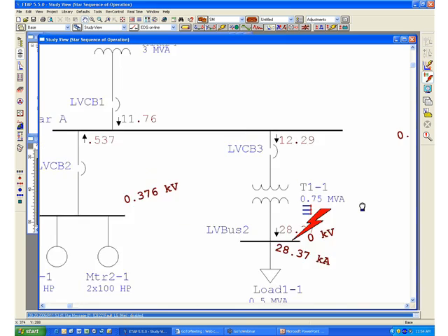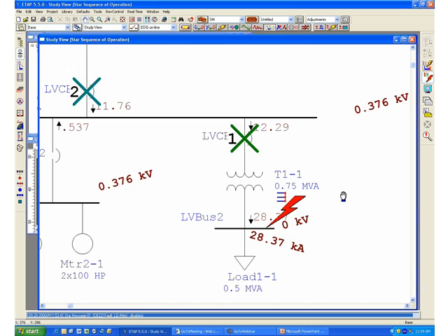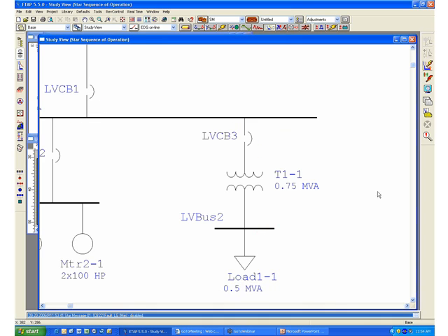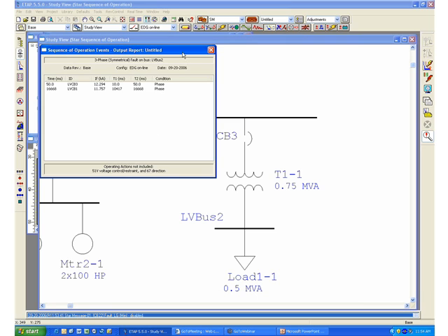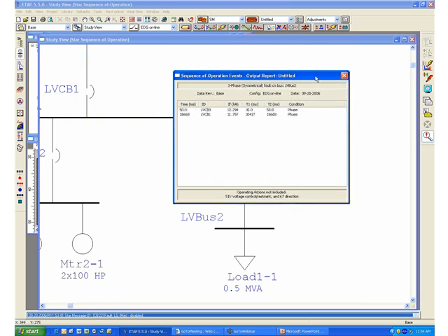We can also check how fast LVCB3 will respond in the event of a regular short circuit on LV bus 2. If you go to our sequence viewer, we can determine how long it took for LVCB3 to operate.